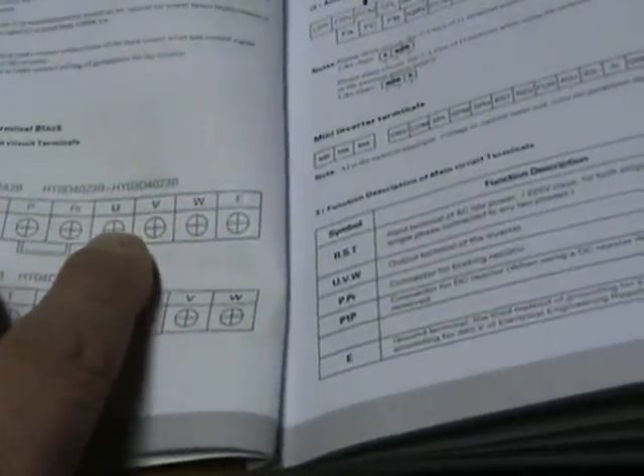The furthest one to the right, the E, is your ground or neutral ground. So for three-phase you'll have R, S, T connected; for single phase you're going to connect R and S, and then your neutral ground will go over to the E. The P and PR are for a braking resistor, which we're not using, and then U, V, and W are for the outputs to the spindle for the different phases.